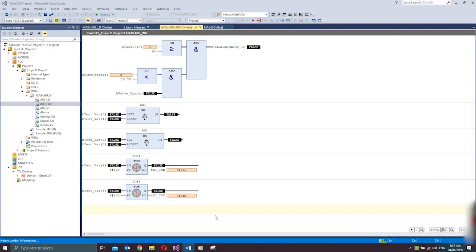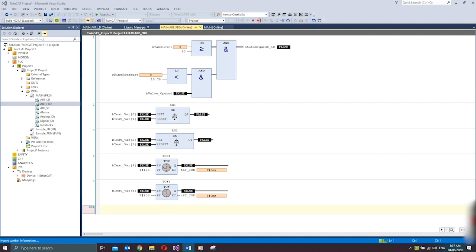So here's how it works. Now, what I did is I assigned the same Boolean variable I used on the on-delay timer above, so we could see the difference between TON and TOF. Also, the preset time of each timer is set to a constant value of 10 seconds. Okay, so let me just turn the input into true. Write the true value. As you can see, the output of the on-delay is not yet true, while the off-delay is already true.